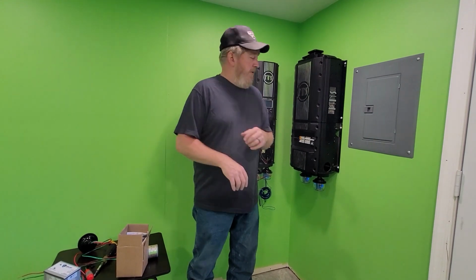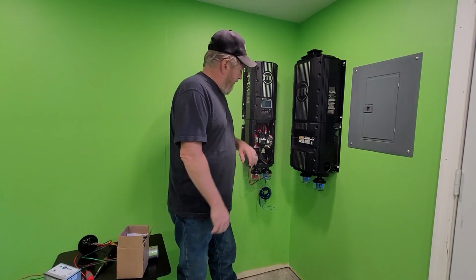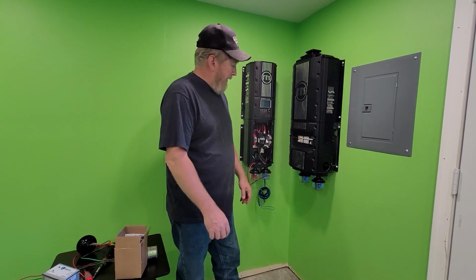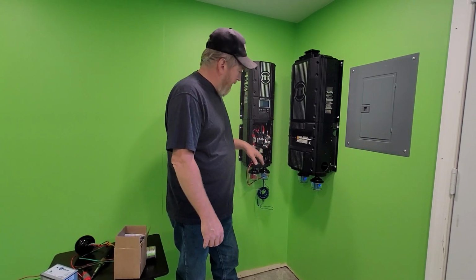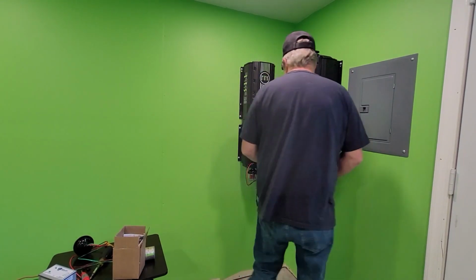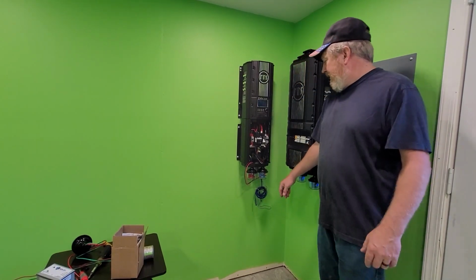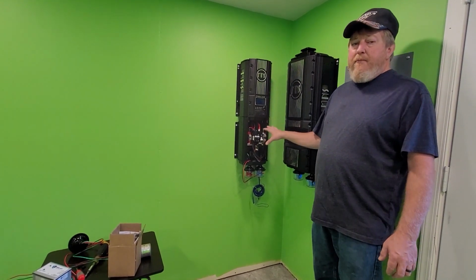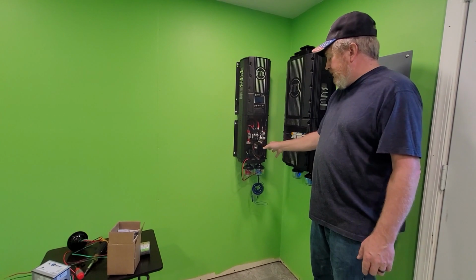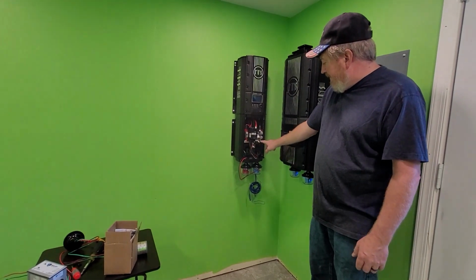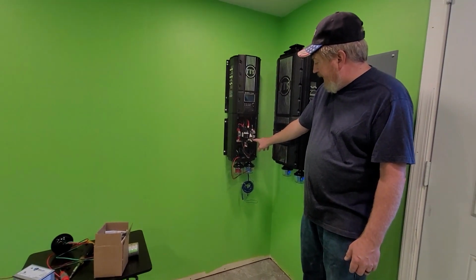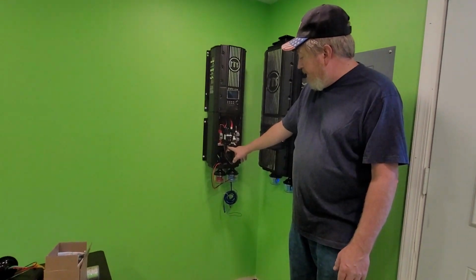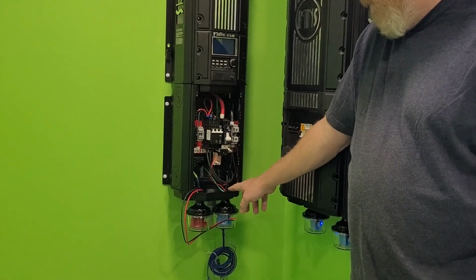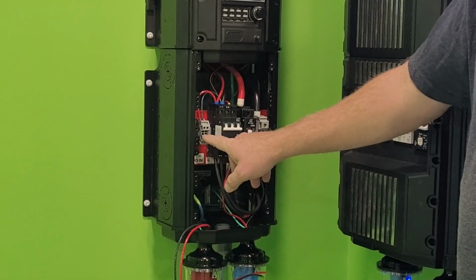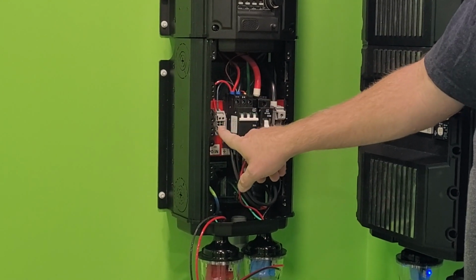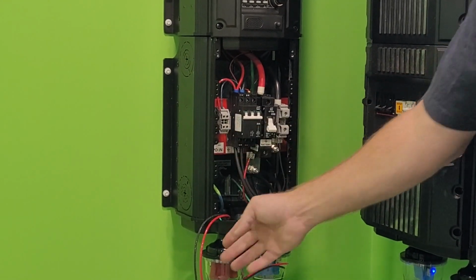But we're trying to focus mostly on the SPDs, where you install them and how you install them. So I'm going to move around a bit so I can do some pointing. You'll notice in the Hawke's Bay breaker box, this is a 600 volt charge controller - Midnite is giving you a lug here for your negative SPD, a lug here for your positive to your battery on your SPD, and then this little jumper block here for your 600 volt on your SPD.